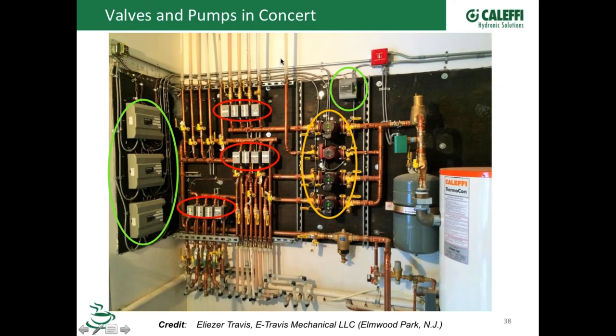So he's got one pump that's just going out to a single zone, maybe an air handler or something like that. So he's got a single zone relay for that pump right there. And these other ones are being controlled via zone valve. So the zone valve opens up, it calls on through the relay box, calls on the appropriate pump.